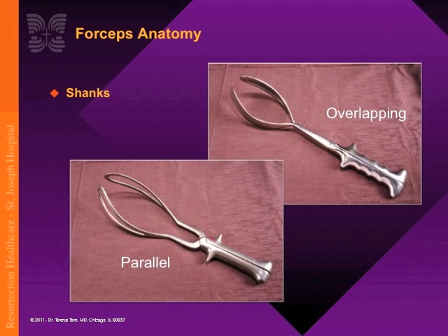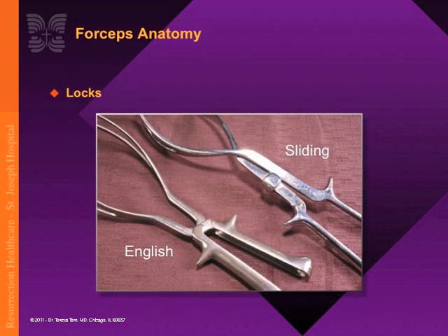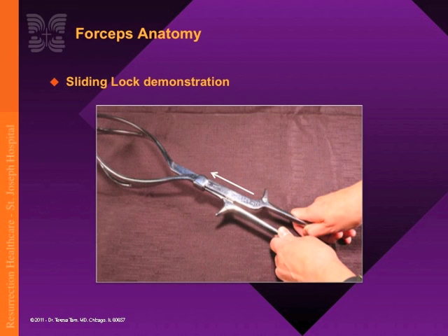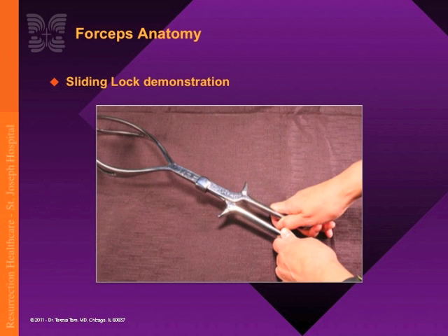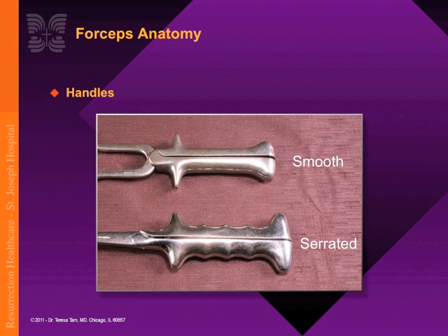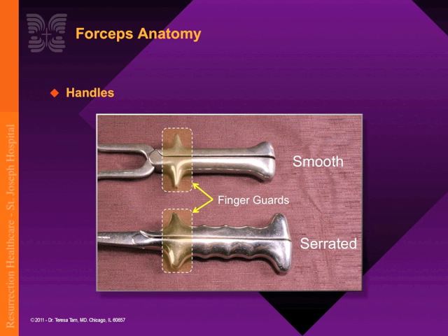The shanks could either be parallel or overlapping, and mainly determine the type of classic forceps instrument. There are only two types of locks currently used: the English lock and the sliding lock. All classic obstetric forceps have an English lock. The sliding lock is seen with Kielland forceps. The fourth part is the forceps handle, which could either be smooth or serrated to enhance grip. The handles allow ease in applying the axis traction principle during traction.